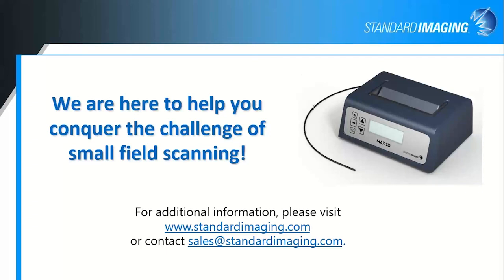How long can you use a CLR measurement before you need to take a new one? The degradation of the fiber in terms of signal output is about 2% per kilogray of dose to the fiber. And that's really just due to the slight yellowing of the plastic, that it gets a little bit colored, a little bit cloudy under irradiation. It's the discoloration of that fiber that affects your Cherenkov light ratio because it affects the balance of the spectrum that gets transmitted through the fiber. And so I recommend that you check your CLR measurements at least every kilogray or so of dose that you're giving to your fiber, but it shouldn't change drastically over that time.